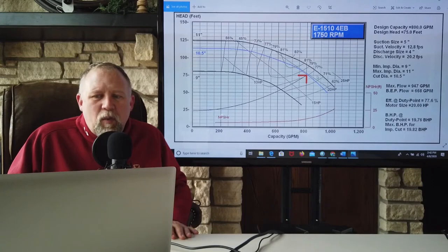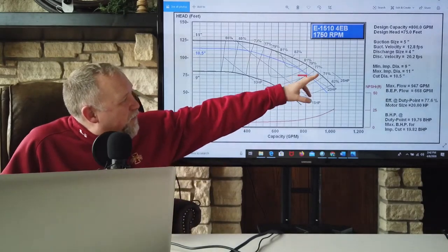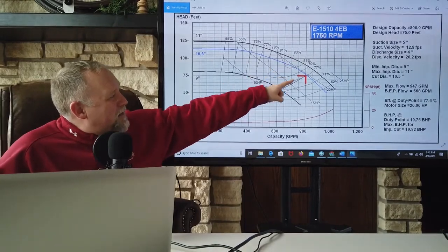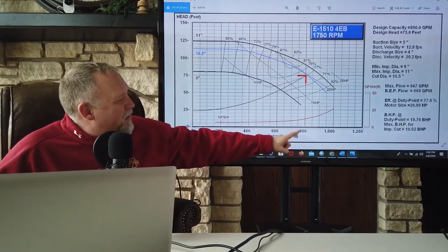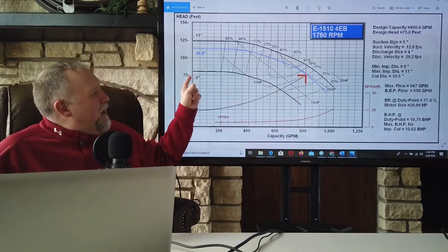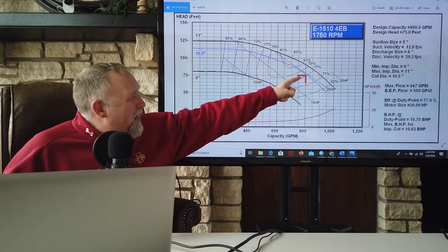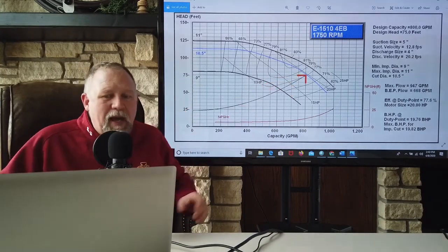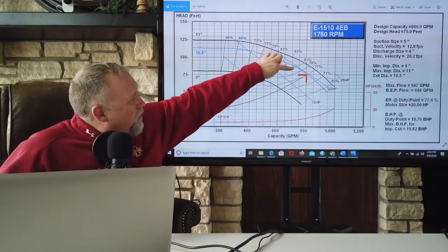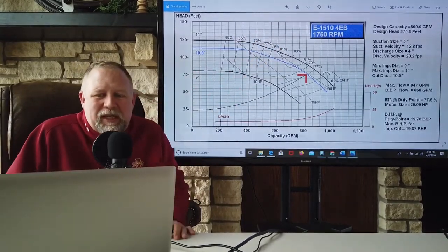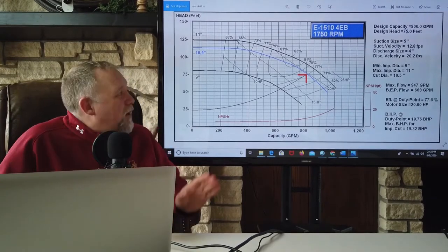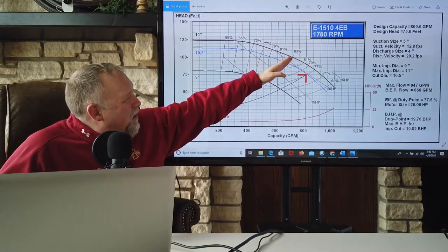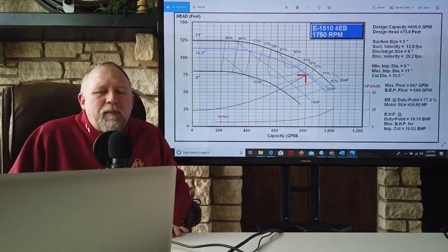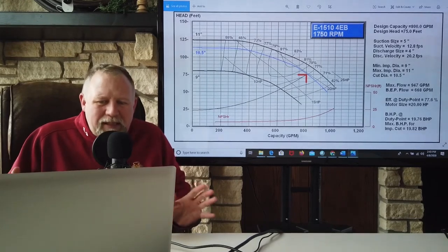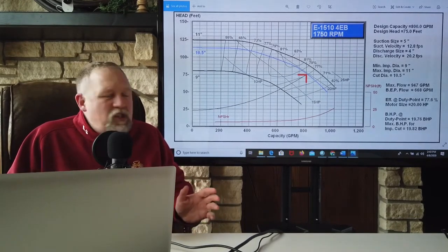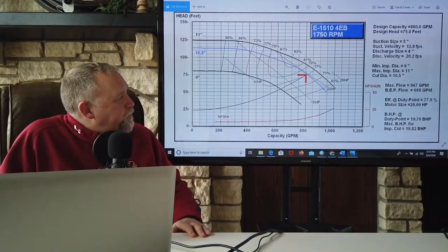Notice on this one, we have selected, if you look at the far right side at the top, it has a design capacity of 800 gallons per minute at 75 feet of head. That is where the pump will be operating. Now, notice, you see these curved lines. Those are lines of pump efficiency. The best efficiency point on this pump would be right here in the middle. So as you're picking pumps, you want to pick them with the best efficiency point possible, but there's going to be certain ranges of acceptable that you can operate a pump at.